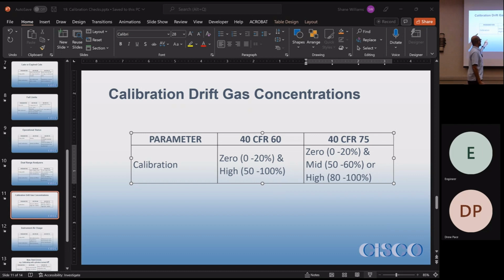I'm either consistently right or I'm consistently wrong. So, as I said, for the calibration gas on the higher end, regardless of the zeros, the high for Part 60 is a straight 50 all the way to 100%. Part 75 allows you to use the mid-range for your daily calibrations, but the wording is, however you want, as much as it represents the stack concentration. But EPA has never shown any exception to using it just as normal calibration regardless. And so the only distinction is that 61 to 79% gap there. But it does afford you, like I said, if you run out of calibration gas, you can always grab your mid-range linearity gas and use that for calibration.